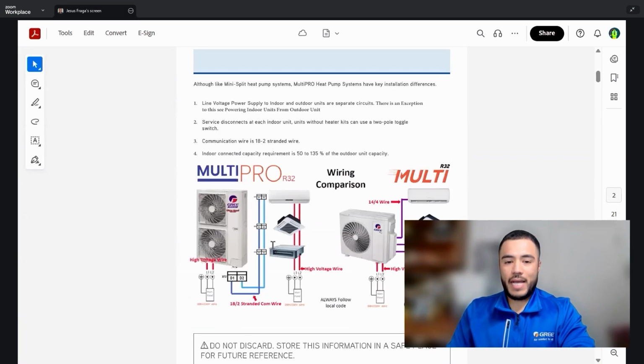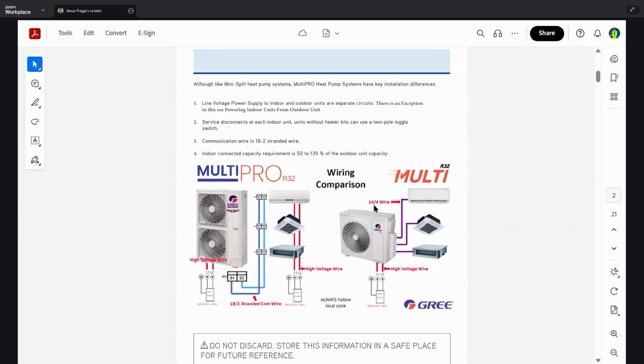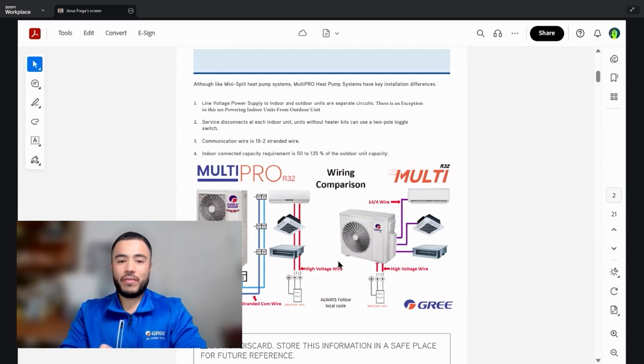Starting off here, as we see, some things change and some things stay the same. In MultiPRO R32, we have a communication data chain that goes to the indoor units, and we still have our line voltage power. To compare that to multi-zone mini splits, multi-zone mini splits use 14/4 communication wire and power. That means this wire has 4 conductors: one is used for communication, one for ground, and the other 2 for power. The main difference is the communication method used. One uses the 14/4 as I stated, and the other uses the 18/2 stranded communication wire. Now with R32 MultiPRO, there's an added feature where you can power the indoor units via a terminal block at the outdoor unit.